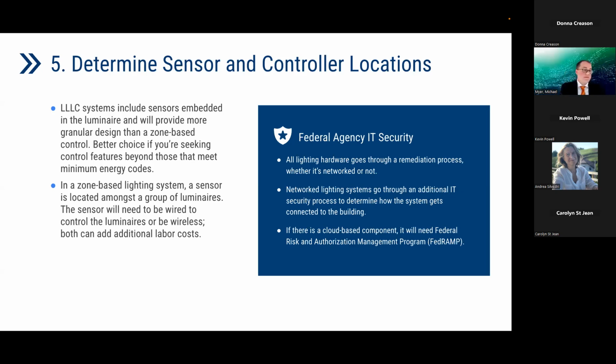Why luminaire level controls? The idea is that now I don't have to do as much thought process. I don't have to think about all my zones. I put a sensor in every fixture, and now I can actually do all that design after the fact. Once the building's up and operating, there are some advantages to that. Some of the energy codes, such as ASHRAE 90.1, are requiring occupancy sensors in open plan offices with zones no larger than 600 square feet. That kind of starts pushing you to this type of design, because now your zone size is so small, luminaire level makes a lot more sense. Zone-based also has a great advantage in conference rooms and other types of spaces.